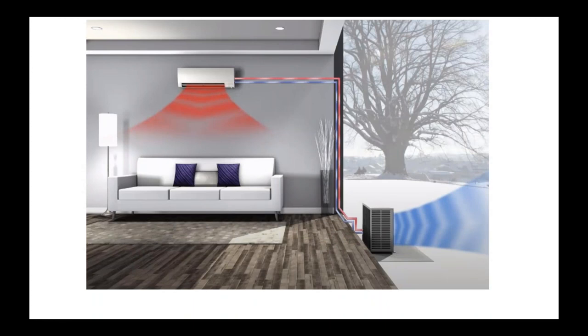So just to get to how they work, this is the first step into the components of the system. You'll see that the indoor unit is positioned high up on the wall and the outdoor unit is outside. And of course, in New England, we really want to mount these units up off of the ground high enough where they're not going to be drifted in with snow, and that any condensate from the outdoor unit when it goes into a defrost cycle drips down onto the ground and can form ice without any risk of growing up into the unit.